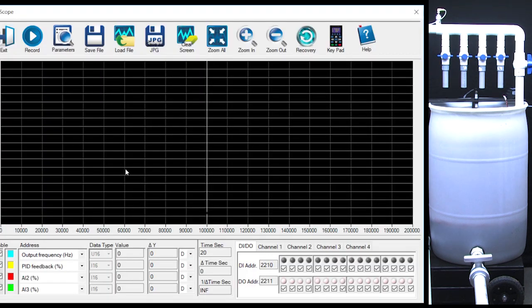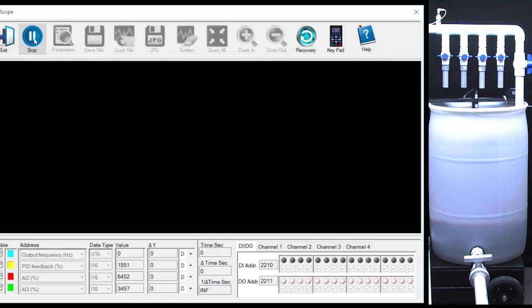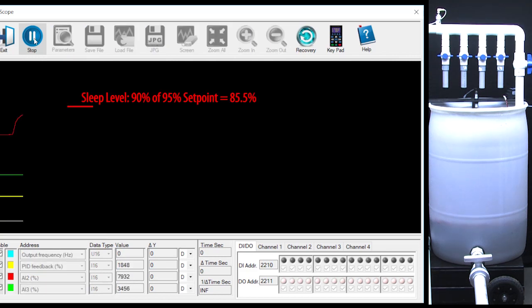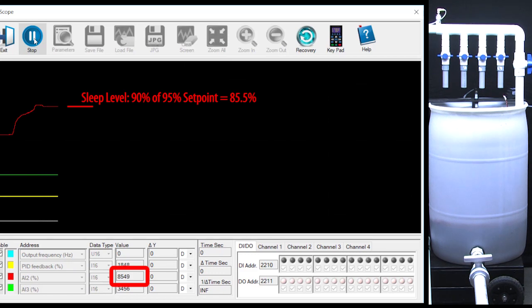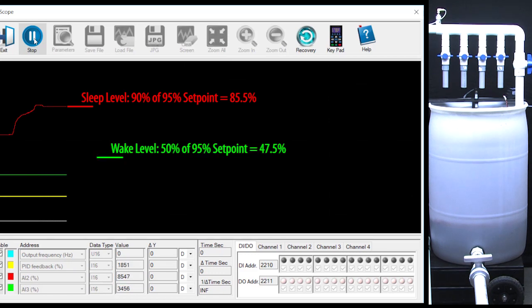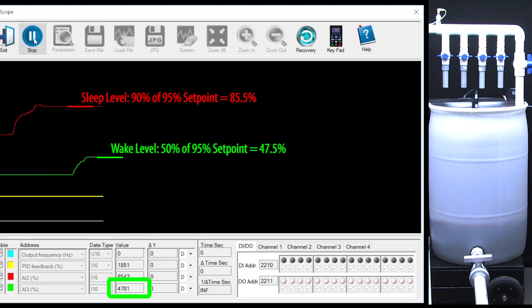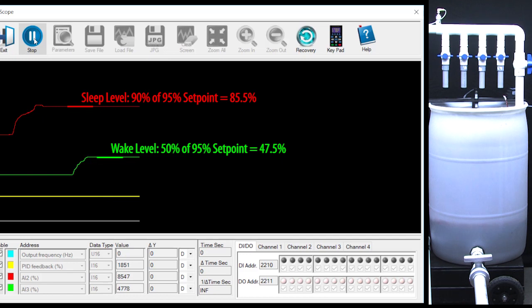Let's bring up the GSOFT2 scope function and set our potentiometer values to mark the sleep level at 90% of our 95% set point which is 85.5% and the 50% wake level which is 47.5%. So now we can see if things change when we expect them to on the GSOFT2 scope.